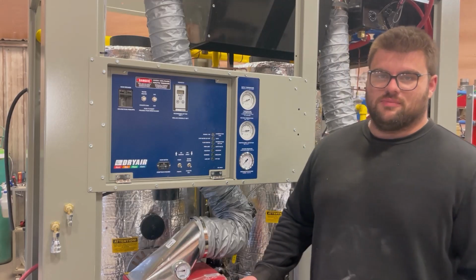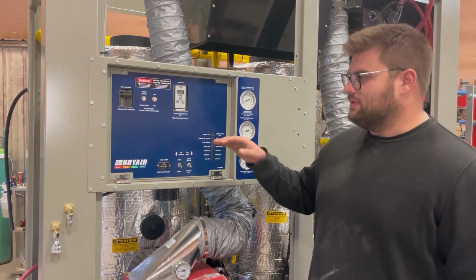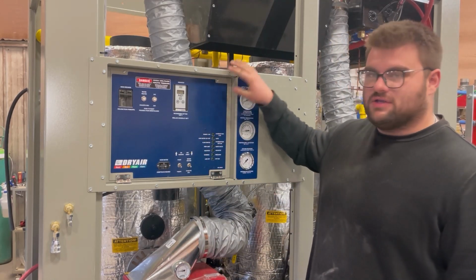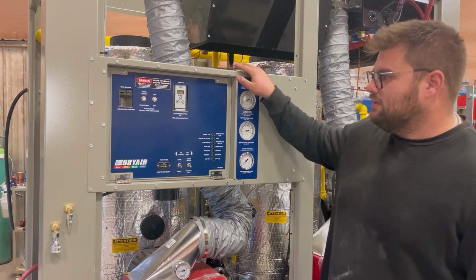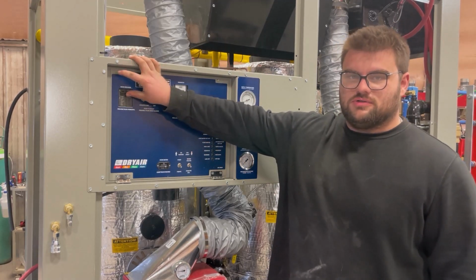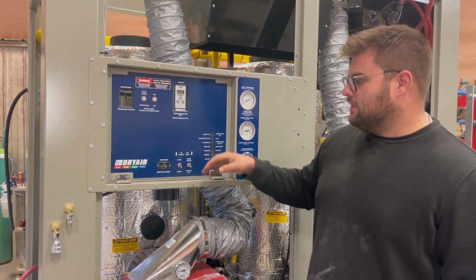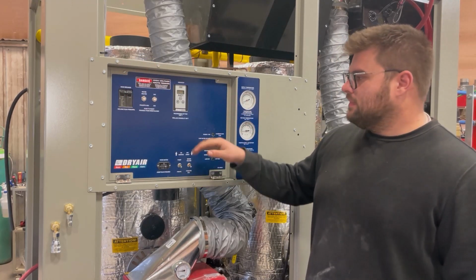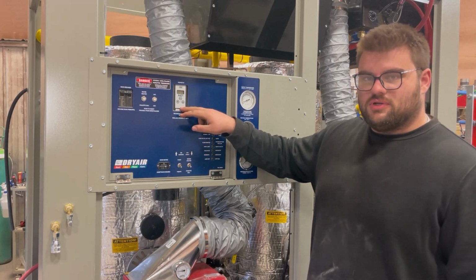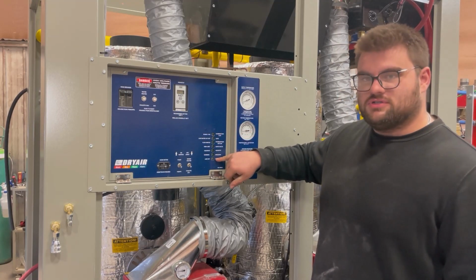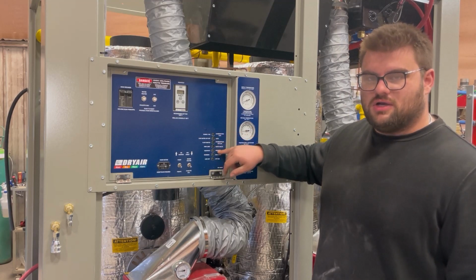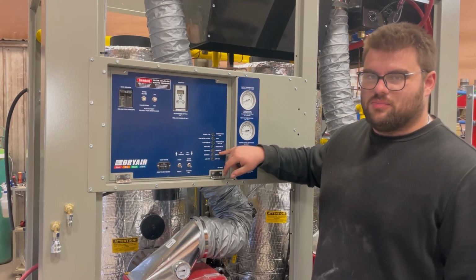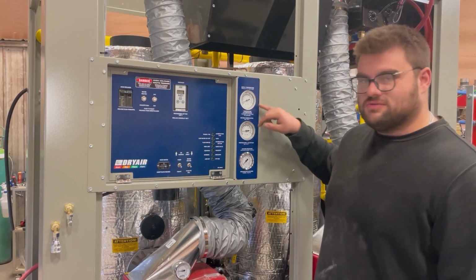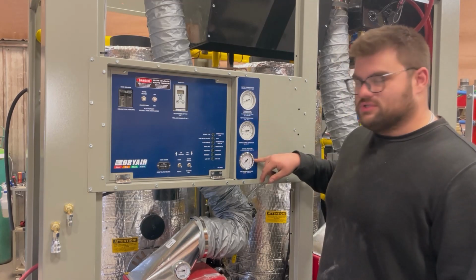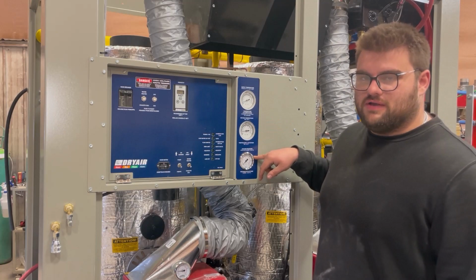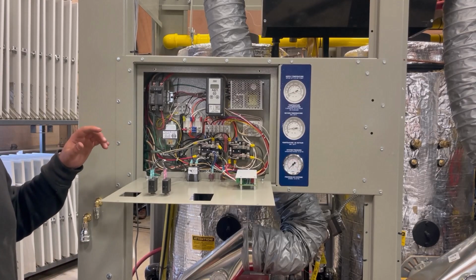Here we are on the Hydro Heat Pro. We don't have a cabinet on this unit, so we can see a little bit better inside. Here we have the control panel, main controls for the unit. You have your main breaker switch to turn 240 volt to the rest of the control panel. You have your pump and water heater switch, your main temperature controller, as well as 7 troubleshooting lights. The 6 top lights will be on in green when the unit's running properly. We have 3 gauges for return and supply temperatures, as well as your system pressure that should run around 35 psi.